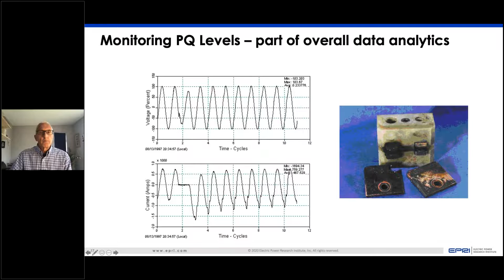In this case, a power quality variation with a short interruption in current and an associated voltage sag downline from where that interruption occurs was an indication that a tap changer on a transformer voltage regulator was failing. Seeing it in the power quality monitor, which happened in Austin, Texas, allowed the utility to take that transformer offline and replace it before it exploded or caused a total outage. They saved a lot of money with their power quality monitoring as a result.